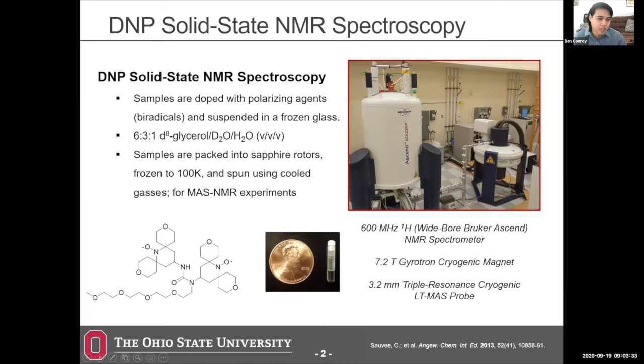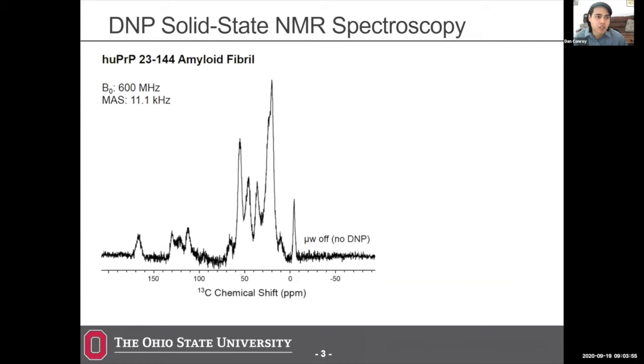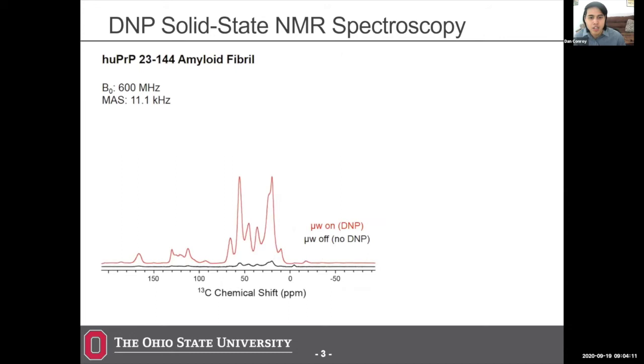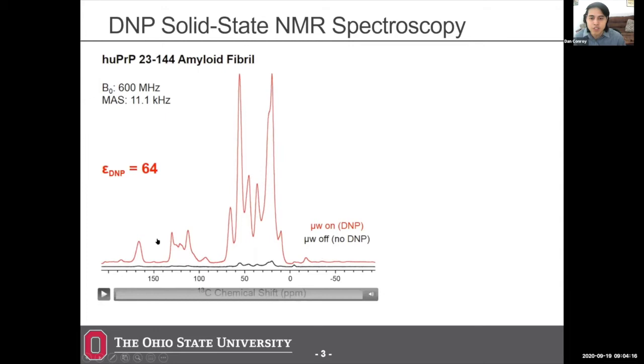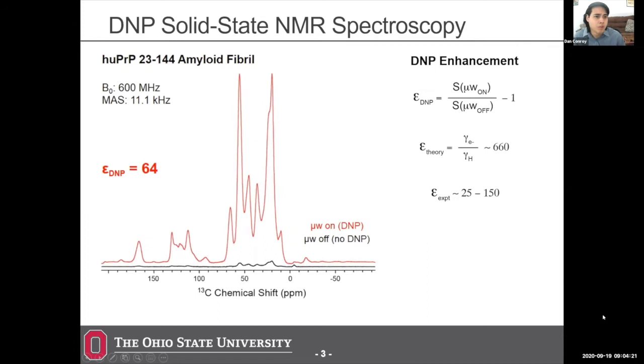The actual effect of DNP NMR is that we get a large signal enhancement. This is a spectrum of a protein sample — this is the signal with the microwave off at 100 Kelvin from a 1D CP experiment, and when we turn the microwaves on we get a very large DNP enhancement of 64. We measure this by taking the ratio of signal with microwaves on to signal with microwaves off. In theory this enhancement is related to the gyromagnetic ratio of electrons to protons — on the order of 660 — but in practice, due to sample effects and paramagnetic bleaching, the actual enhancement is anywhere from 25 to 150.